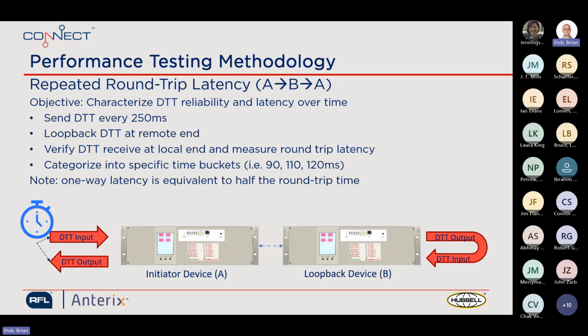At the initiator side, we can measure the time delay between sending the input and receiving that DTT output back at the initiator device, and then categorize the delays into different time delay buckets. This is a two-way, round trip test, so roughly half of that time would be representative of the one-way latency you would see in the field sending from the substation to the generator. The times that we show here are going to be mostly round trip times, so just keep in mind that half of that time would be representative of a real world scenario.